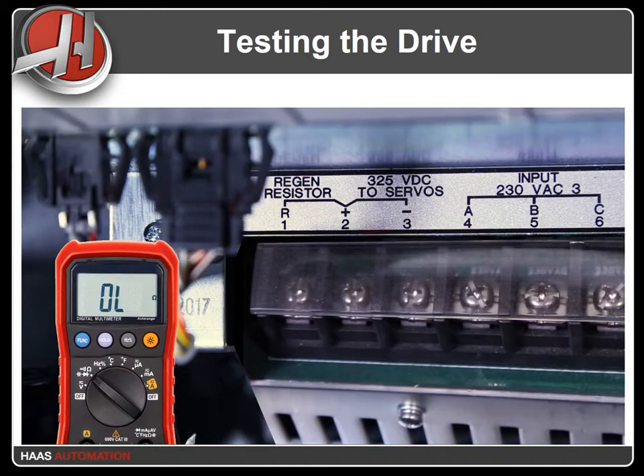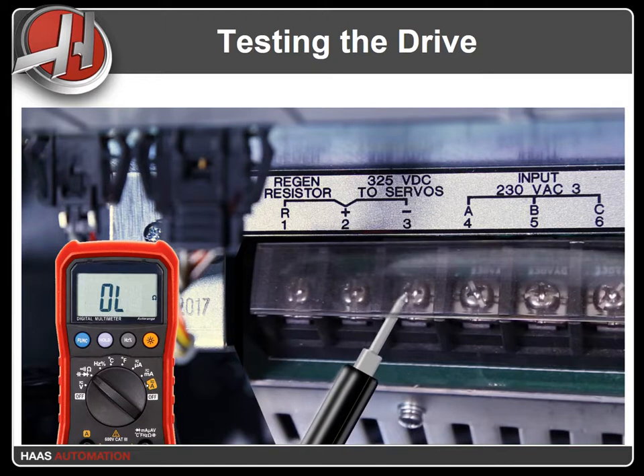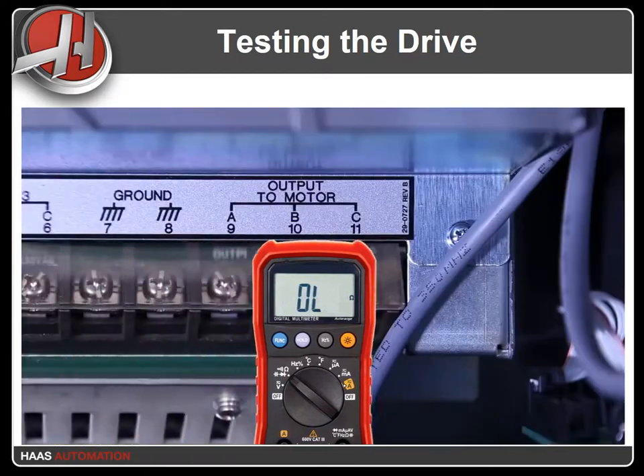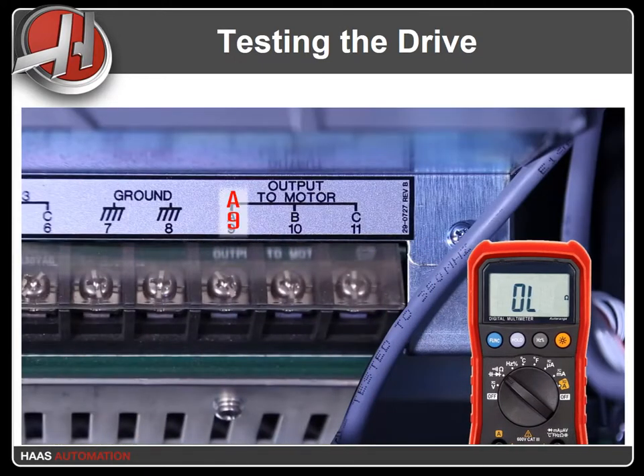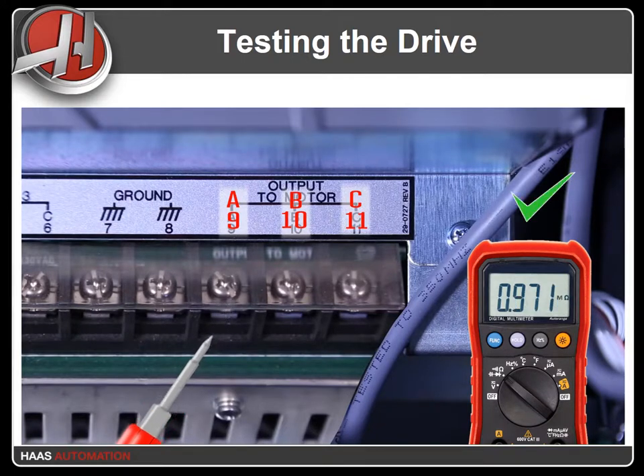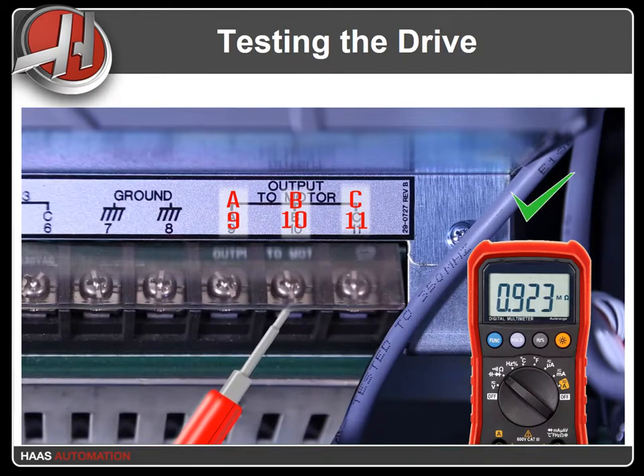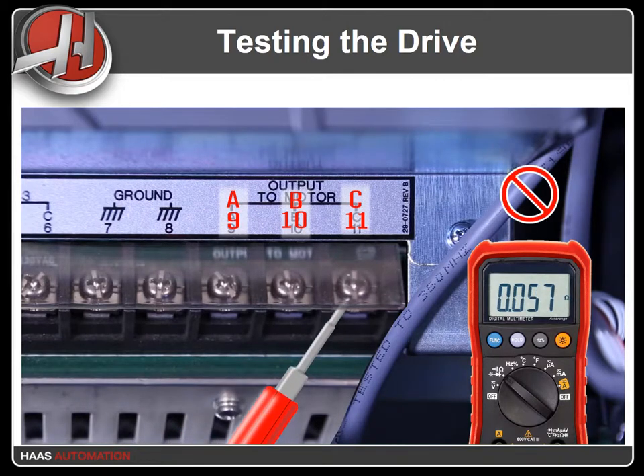Check the output on the negative side of the DC bus. With the multimeter still set to resistance test mode, put the black lead on terminal 3, labeled with a minus sign. Touch the red lead to terminals 9, 10, and 11 again. As in the positive side test, the meter should show high resistance readings, typically in the range of kilo or mega ohms. If your meter reads very low resistance, the vector drive is damaged.